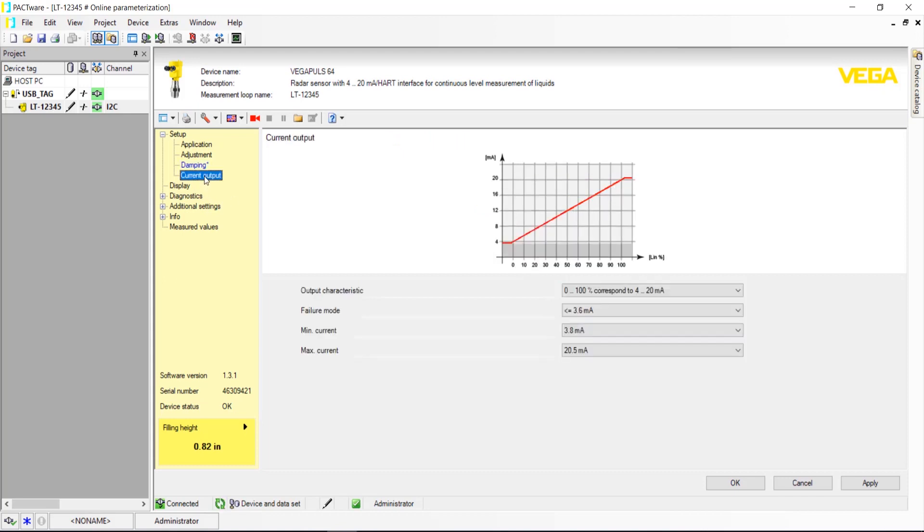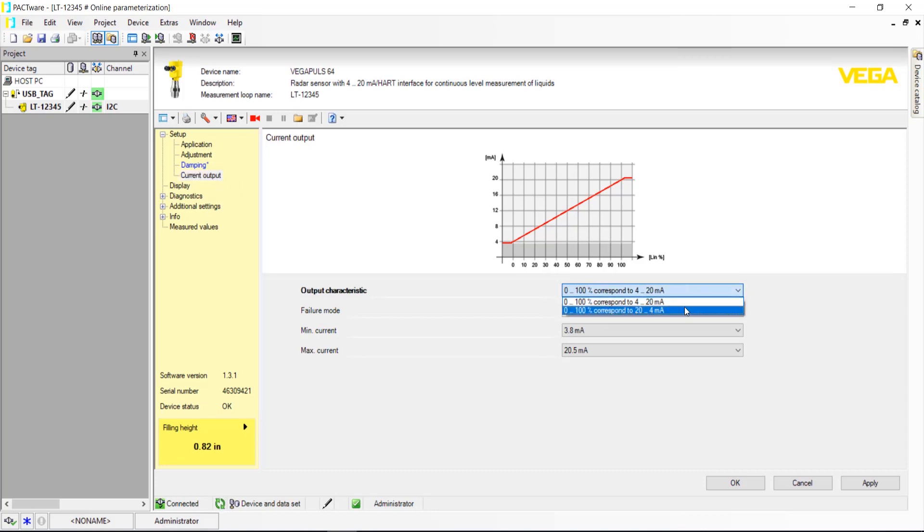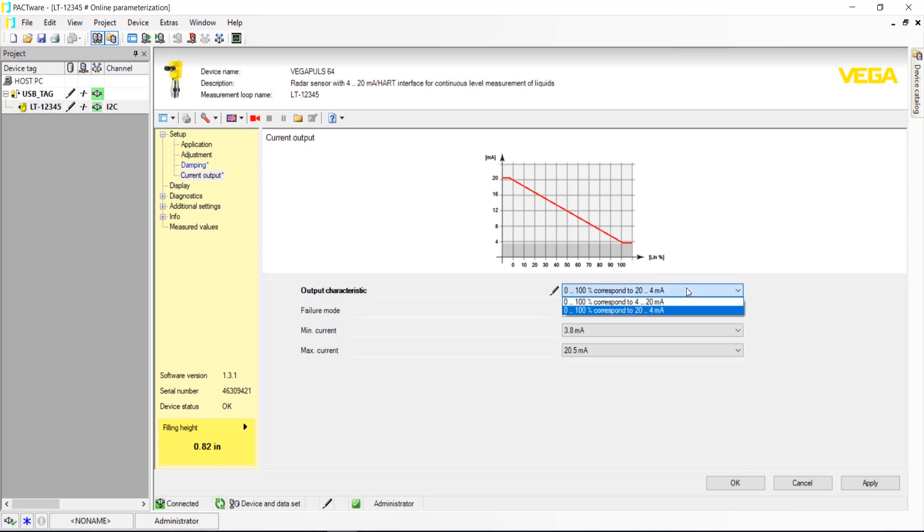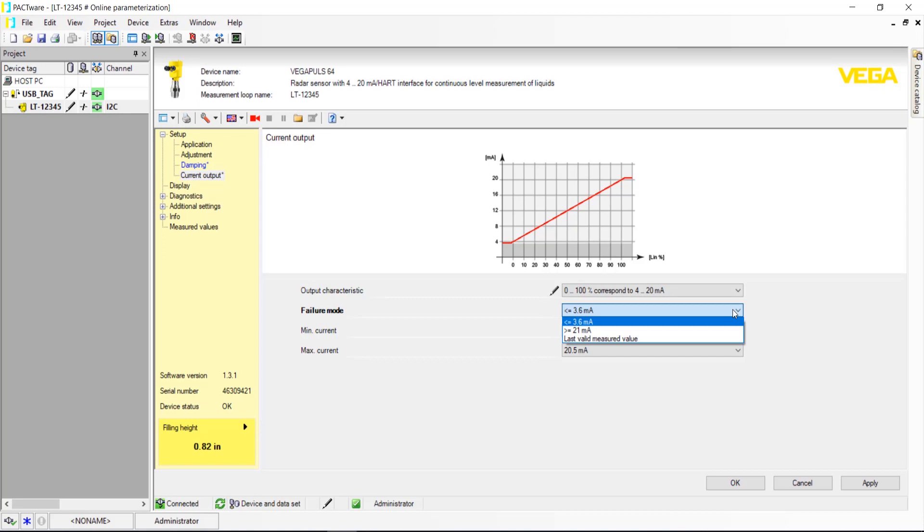Current output is next in line on the Setup tree. Output Characteristic gives you the option to change the current associated with the 100% point and the 0% point. Failure Mode gives users the option to set the current output during a failure.